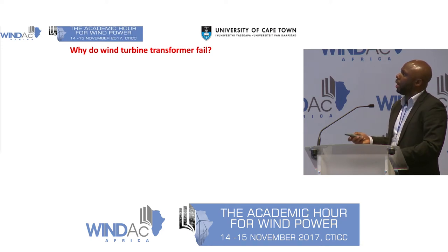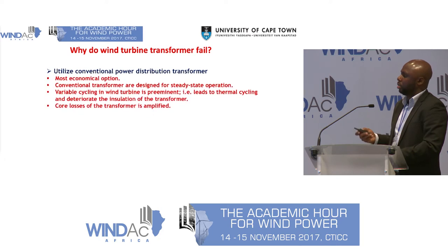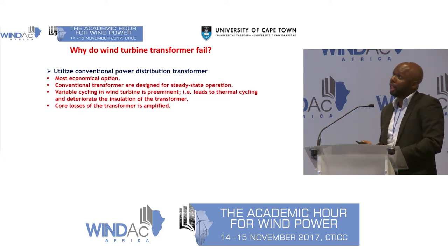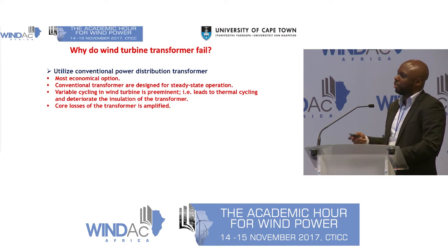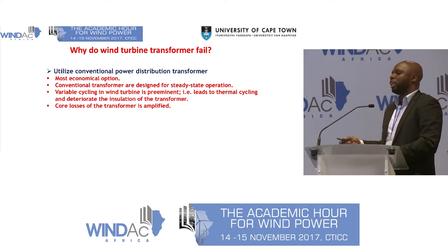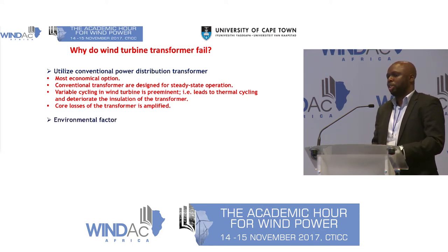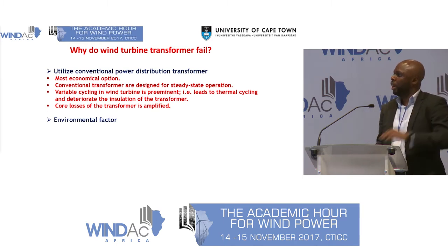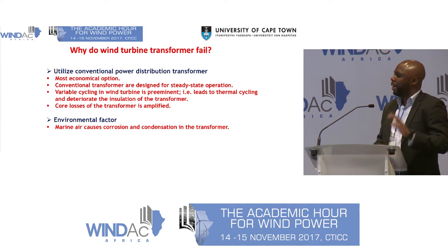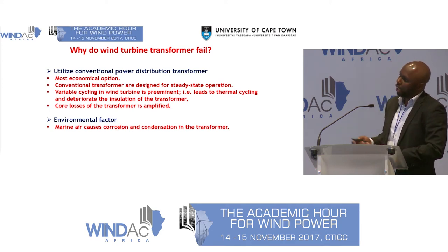Now, why do wind turbine transformers fail? The first reason is, up until recently, most of the wind turbines were actually using normal, standard power distribution transformers. And the reason why developers opt for this option is just because of economics. It's cheaper, but the downside is these transformers are designed for steady state operations, not taking into consideration the variable nature of wind turbines. And another thing is environmental factors. As we know, most of our installations are now going offshore, and by going offshore, they are exposed to marine air, which is quite humid, leads to corrosion and condensation in the cooling medium of the transformer.